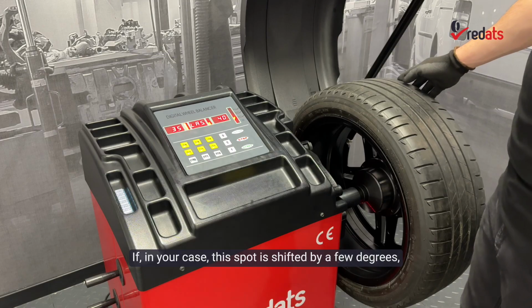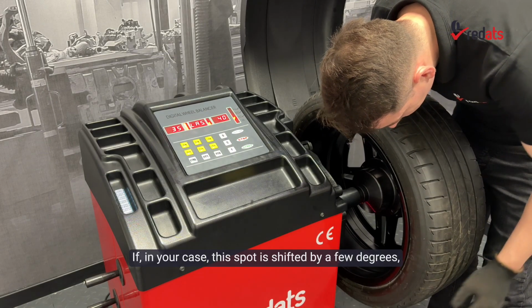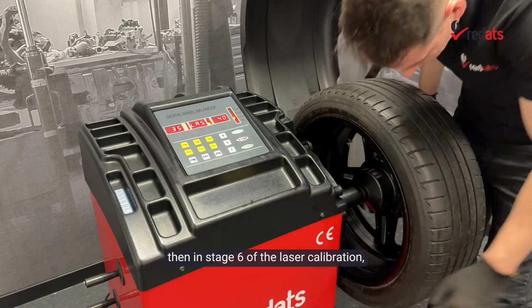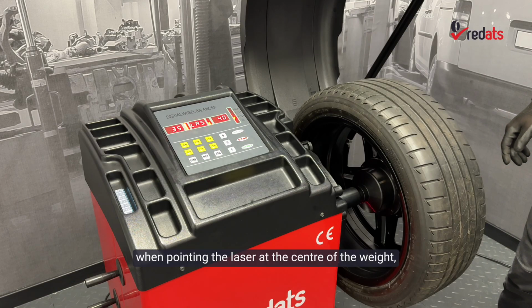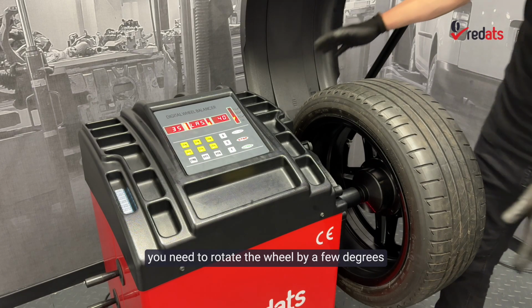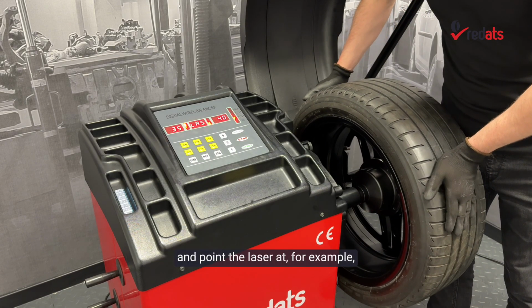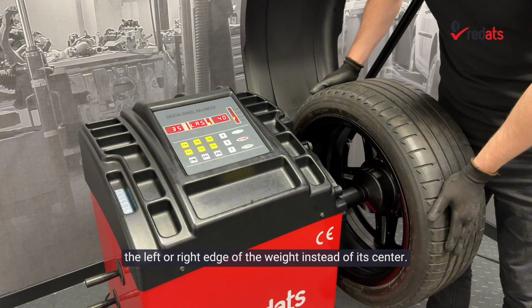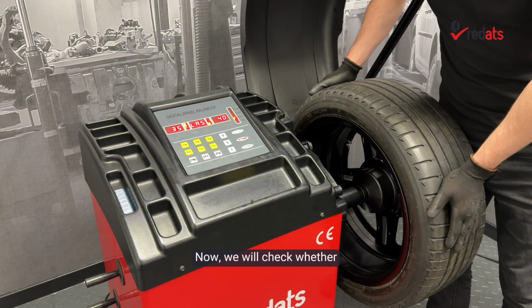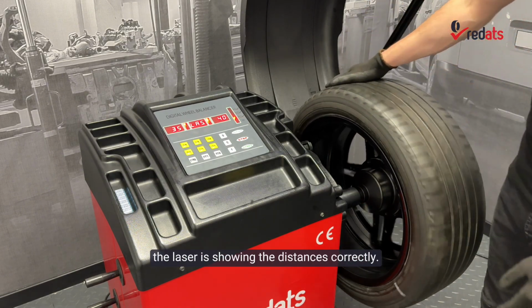If in your case this spot is shifted by a few degrees, then in stage 6 of the laser calibration, when pointing the laser at the center of the weight, you need to rotate the wheel by a few degrees and point the laser at, for example, the left or right edge of the weight instead of its center. Now we will check whether the laser is showing the distances correctly.